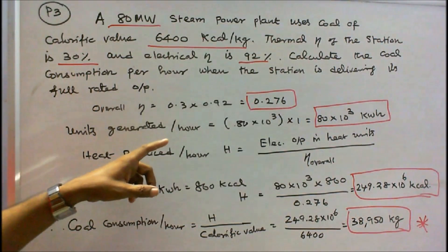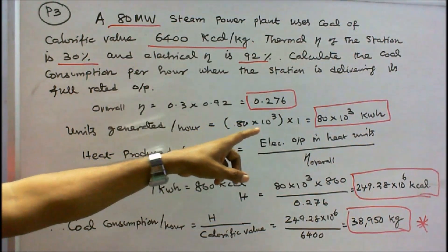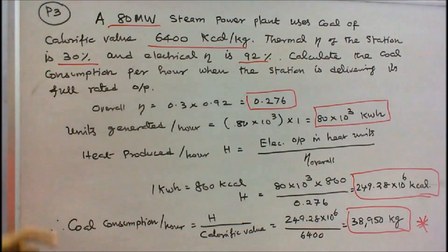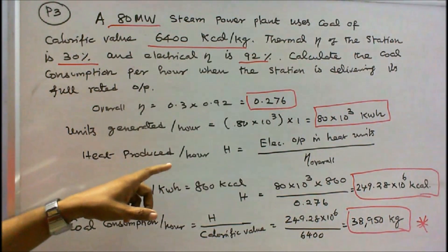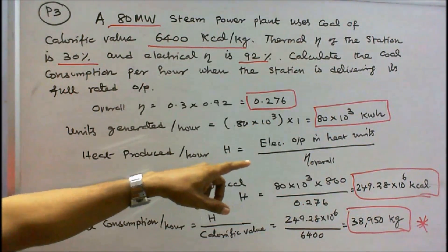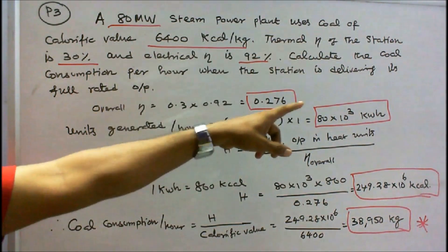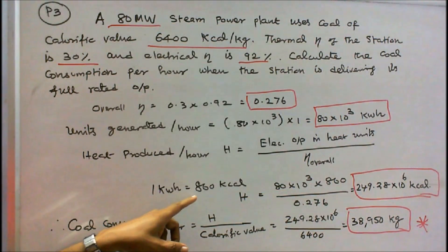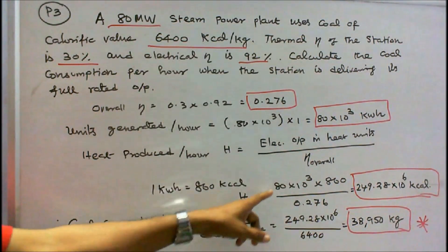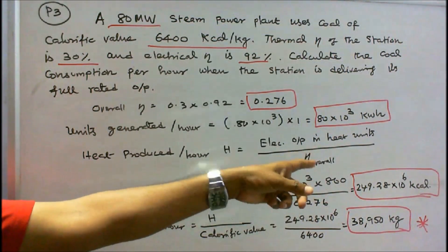Second step: units generated per hour = 80 megawatts = 80 × 10³ kilowatts × 1 hour = 80 × 10³ kilowatt-hours. Third step: heat produced per hour H = electrical output in heat units ÷ overall efficiency. Electrical output in heat units = 80 × 10³ × 860 kilocalories (since 1 kilowatt-hour = 860 kilocalories), divided by 0.276 = 249.28 × 10⁶ kilocalories.